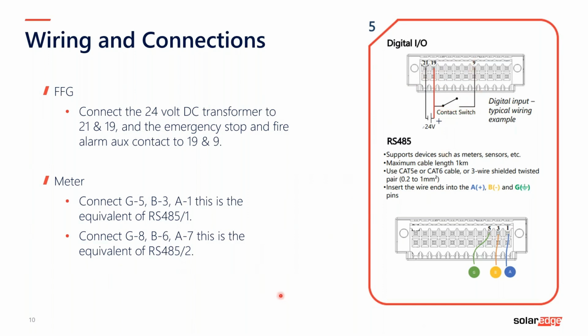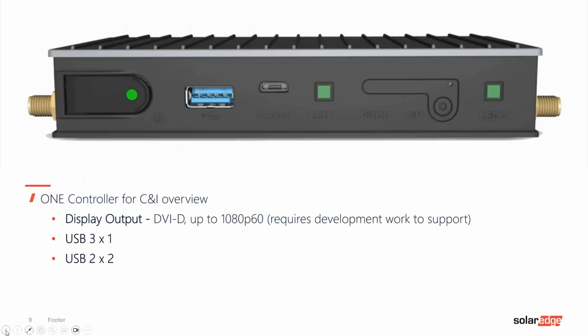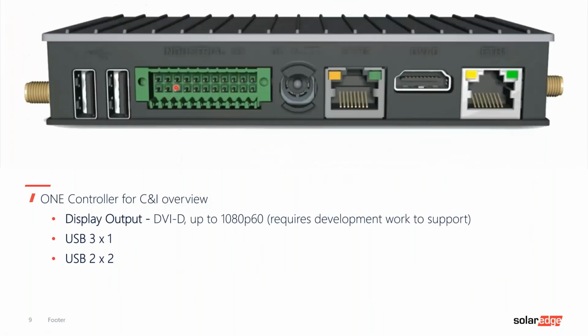Okay. Then looking at the meter underneath, you've got some positions. So this is RS485-1, as we would call it, and this is 1, 3, and 5. Okay, and then you've got RS485-2, which is 6, 7, and 8, and you'll see the positions of those on the next screen. Now, what is most important, and this is really important, is when we look at this screen here, when this spins around, these are the pins we're looking at connecting. So we're looking at connecting that.